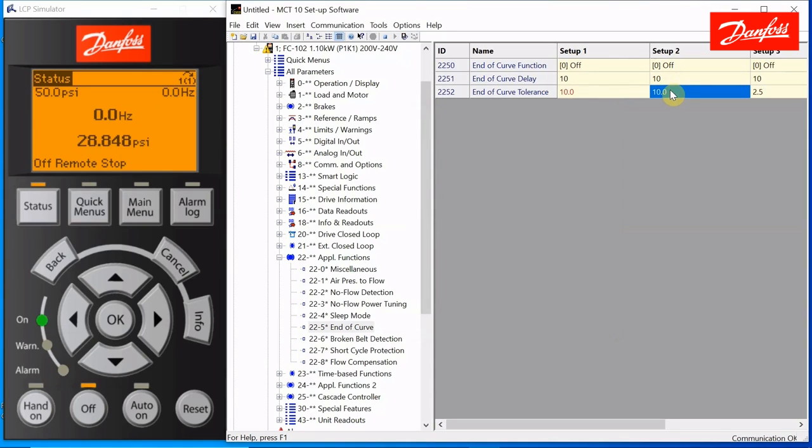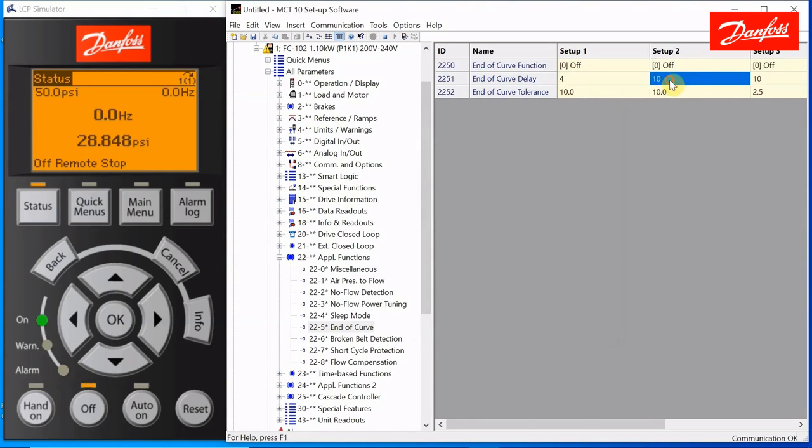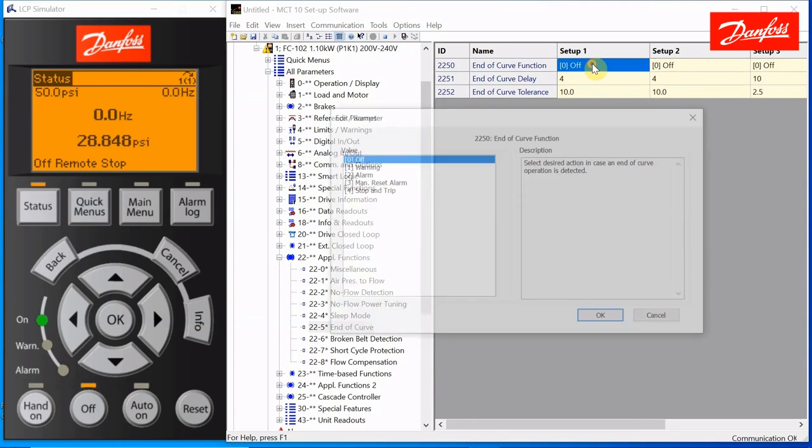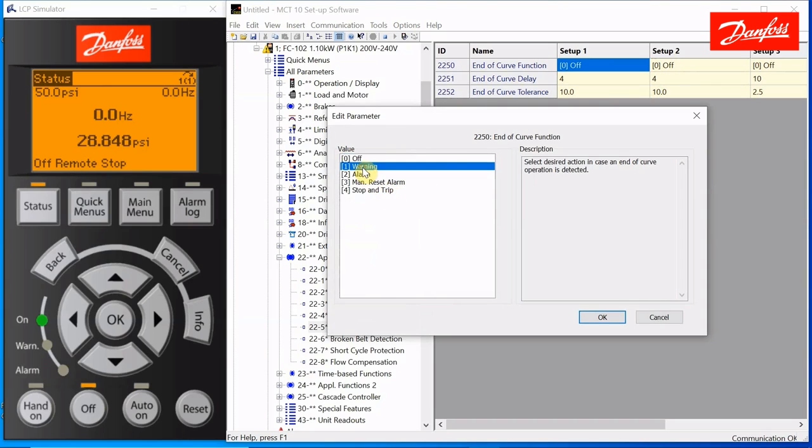And instead of delaying for 10 seconds, let's make it 4 seconds. It'll make a quicker demonstration. And right now the end of curve function is off. That's the default value. Let's look at the choices. You can choose warning, alarm, manual resetting alarm, or stop and trip. Let's just see how they act one at a time.